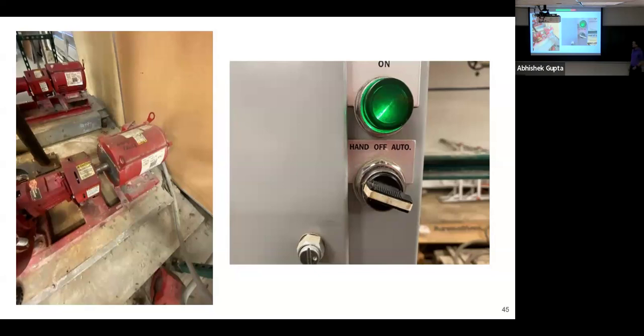This picture on the left is a chilled water pump. I'll give you a clue — look at the picture above it. It's missing the protective housing around the shaft. That shaft has been spinning exposed, and if you have a lanyard on or bend over near it, that's a very risky situation. The pump is actually running, so that's something we'll call out in the assessment.